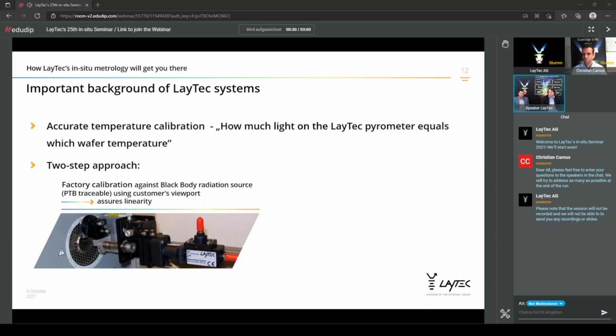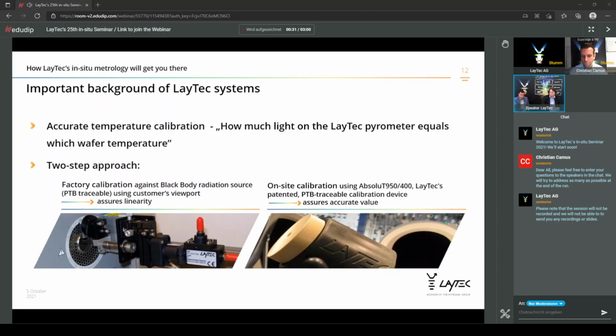And we are using for the calibration the original viewport. So we have a set of viewports for known reactors that we use for the calibration, finally the same optical path that we will find on the reactor after the installation. This brings me to the second step. In the factory, we assure the linearity of the detector, so that we have a correlation between the light intensity on the detector and the temperature. And there are many reasons why we need an on-site calibration as well. The viewports might be slightly different, especially if we have smaller holes in the viewport. We need an on-site calibration.